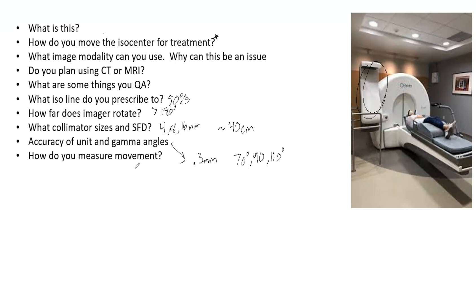How do you measure movement? There are infrared markers on the nose — you can see the marker right there on the patient's nose. Also, these little black bars sticking out into the air each have an infrared marker on them. What I'm highlighting and circling right here is a camera that looks at those infrared markers. If it detects anything greater than 1 to 2 millimeters of movement, the collimators block the source and you have the option to bring the patient out for a rest and then go back in. If the patient coughed or sneezed, they'll eventually return to the correct position and the sources will unblock.